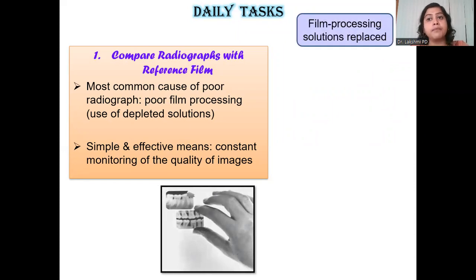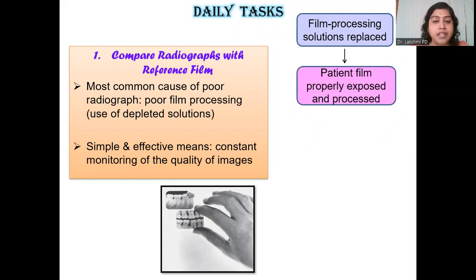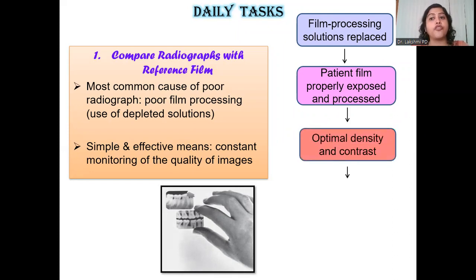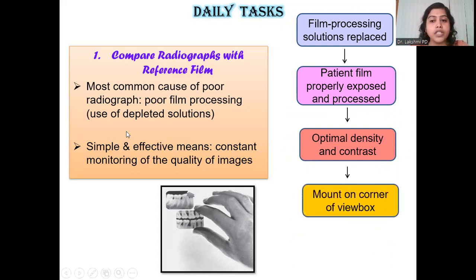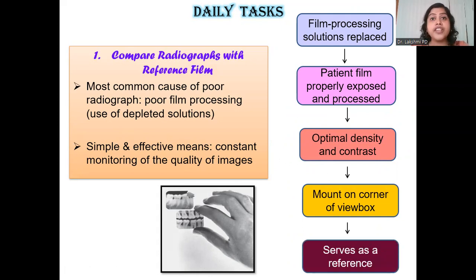For this you will have to take a reference film. Ideally on the day that the film processing solutions are being replaced, take a film of a patient using proper exposure parameters and adequate object-source distance, processed according to manufacturer's instructions. You then get a good radiograph of optimal density and contrast, which you mount on one corner of your view box. This film basically serves as your reference film, and every single radiograph given out from your facility every day must be compared with it to ensure optimum quality, density, and contrast.